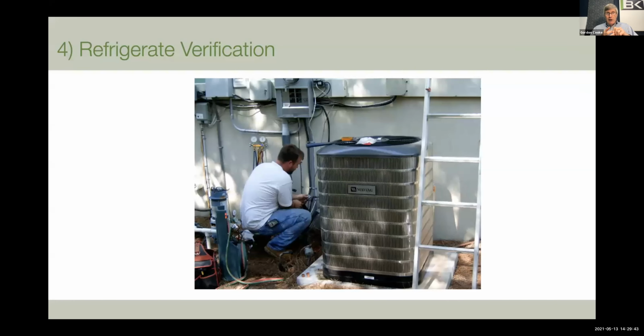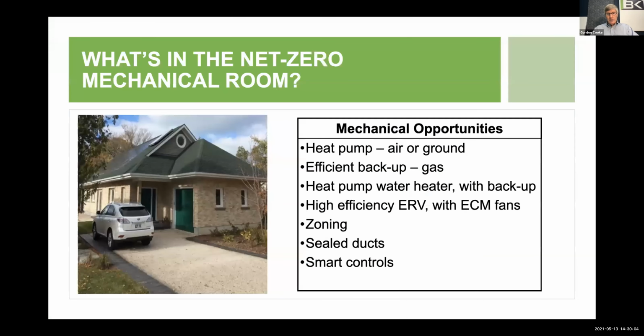Air conditioners are notoriously bad in terms of when do you charge them up? You need to do a commissioning of your air conditioning system at the start of the cooling season. You can't possibly do an air conditioning setup in the wintertime. You can't set it up correctly, or even in the fall. So you should be adding verification to your systems.